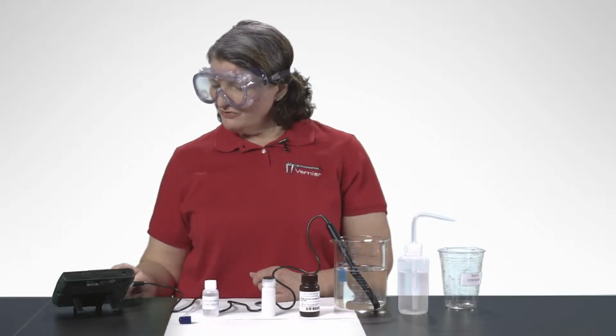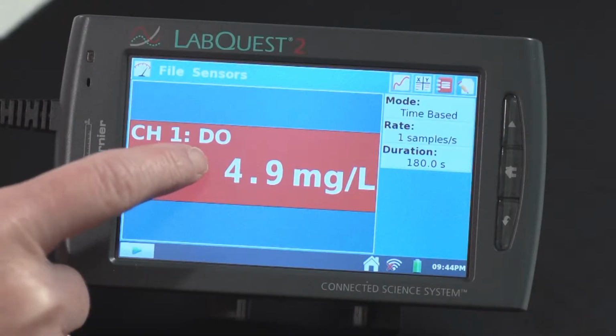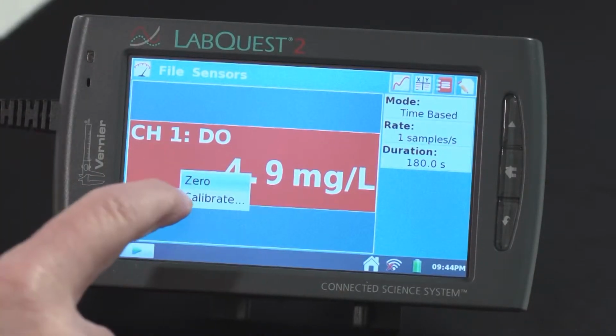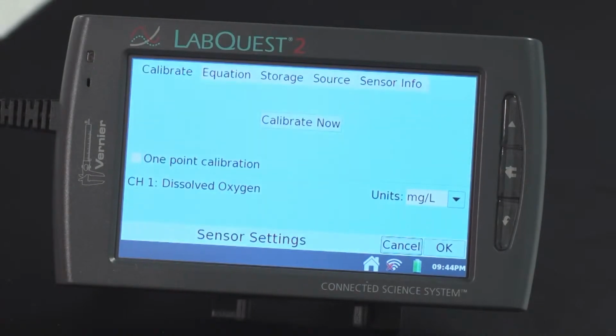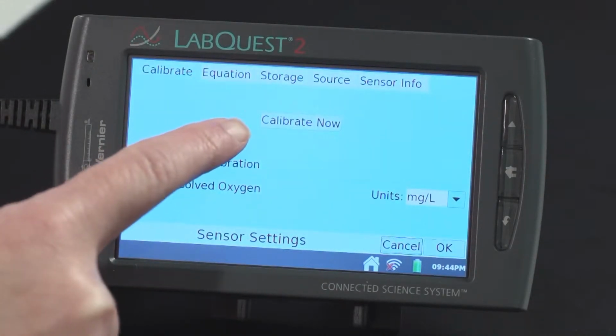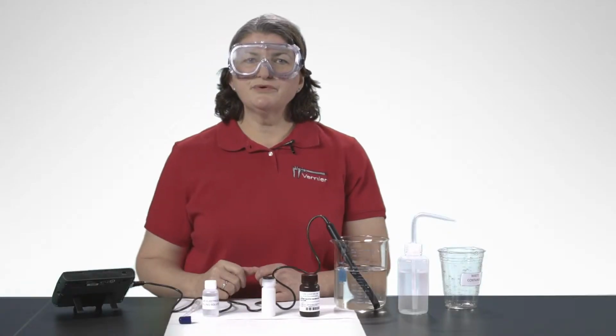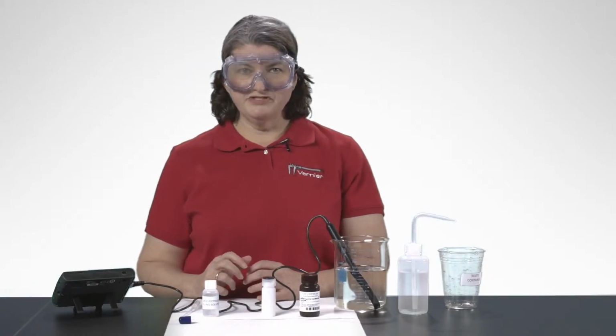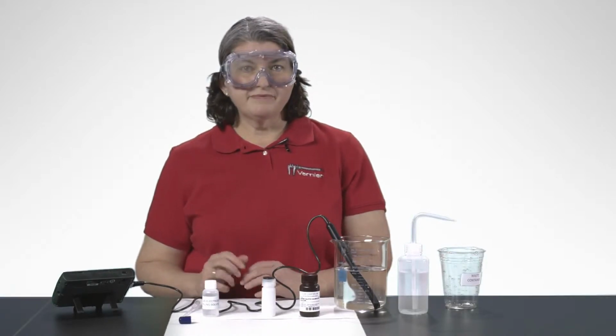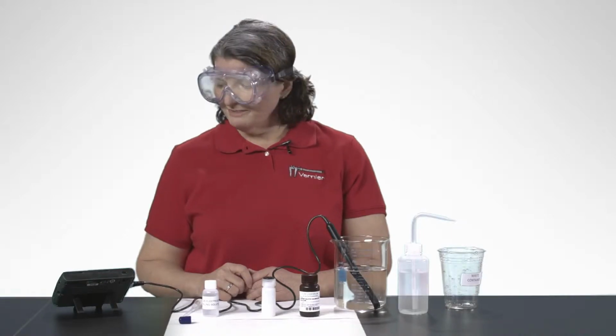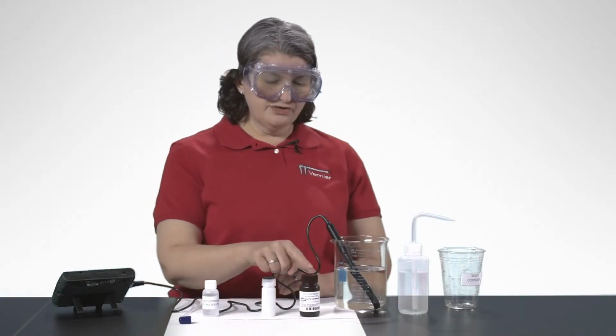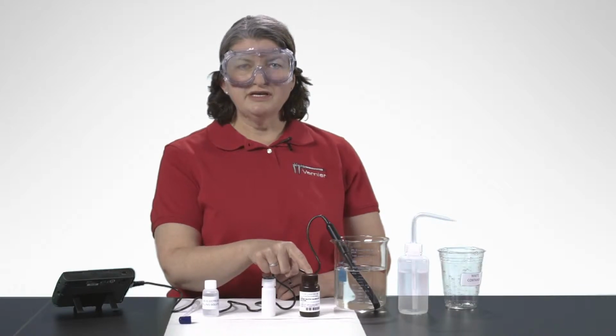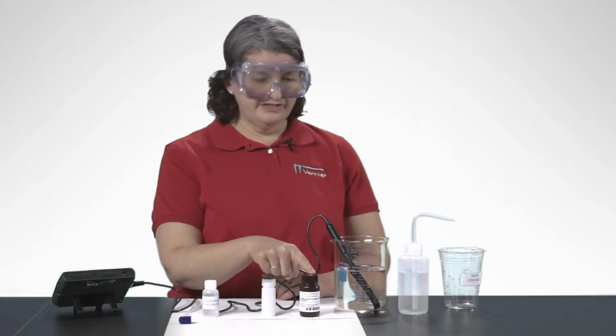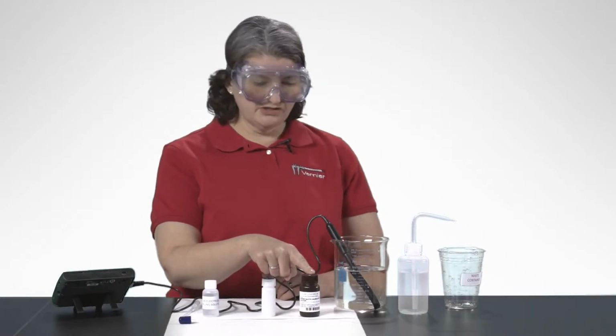So on my LabQuest screen, I'm going to just tap anywhere in the red box and choose the Calibrate option. I'm going to calibrate now. So the idea here is that we're going to put it into 2 known environments, tell the LabQuest 2 what those known environments are, and then it will be calibrated and know how to measure our water. So the first known environment is going to be this sodium sulfite solution. This has no oxygen dissolved in it, so this will be a 0 dissolved oxygen point.